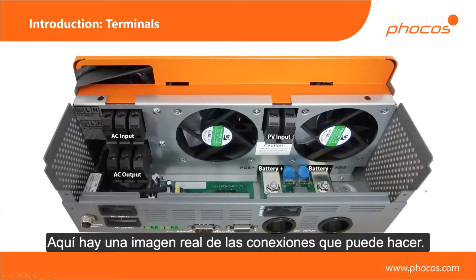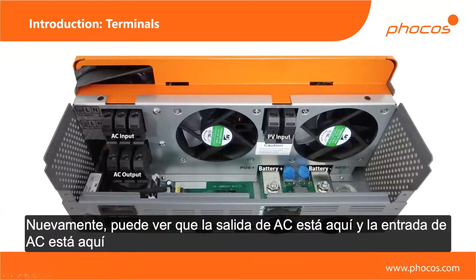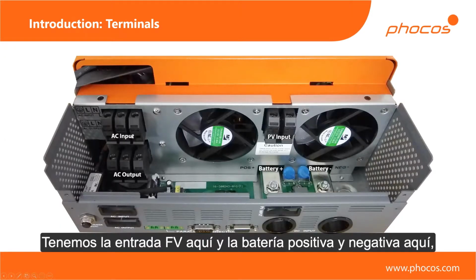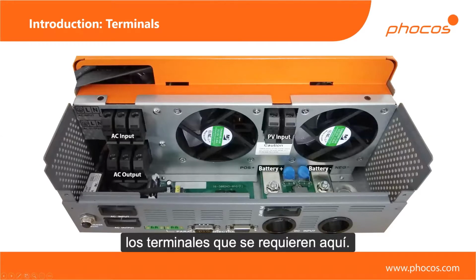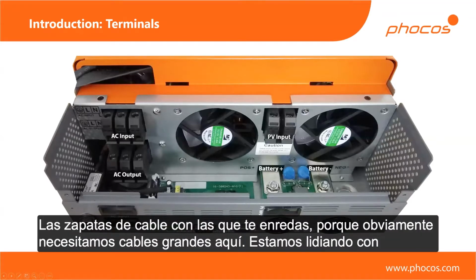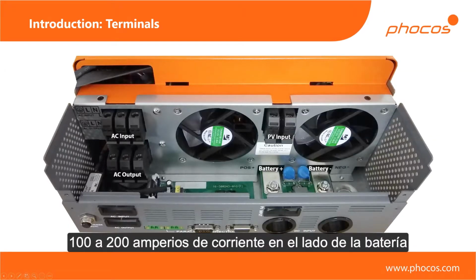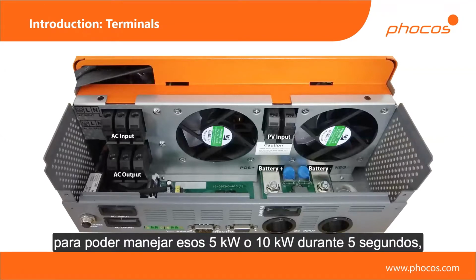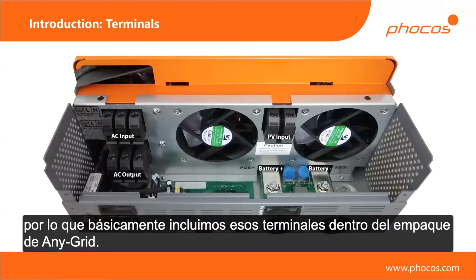So here's a real picture of the connections you can make. Again, you can see the AC output is here, and the AC input is here. We have the PV input right here and the battery plus and minus here. The terminals that are required here, the cable shoes that you crimp around, because we need big cables here. We're dealing with 100 to 200 amps of current on the battery side to be able to handle those 5 kilowatts or even 10 kilowatts for 5 seconds. So we basically include those terminals inside the packaging from the inverter.